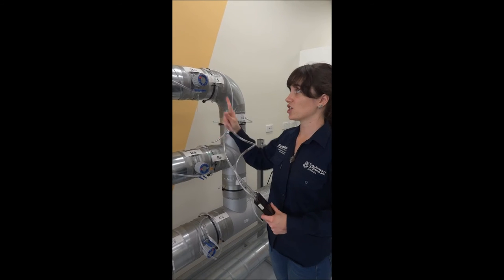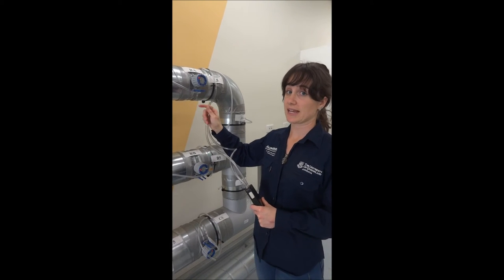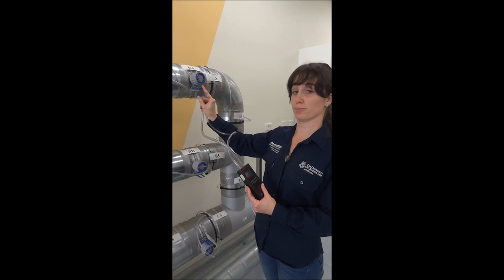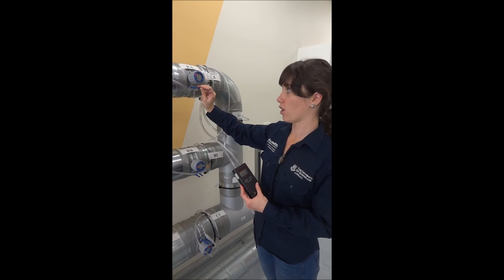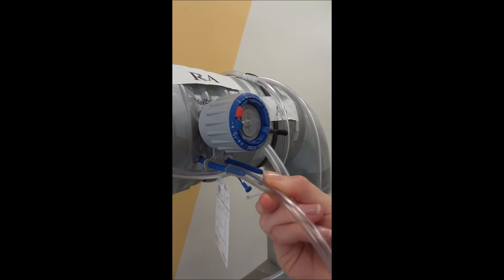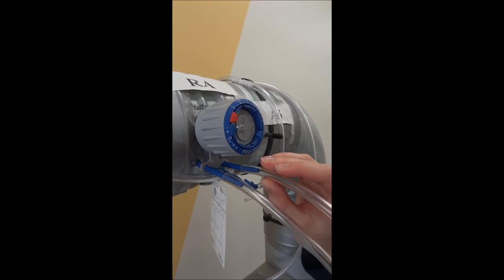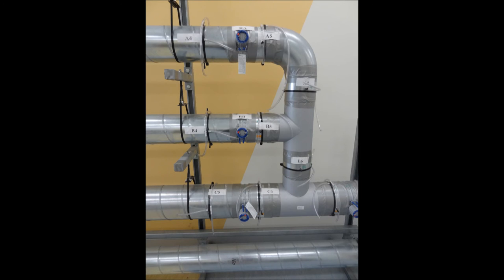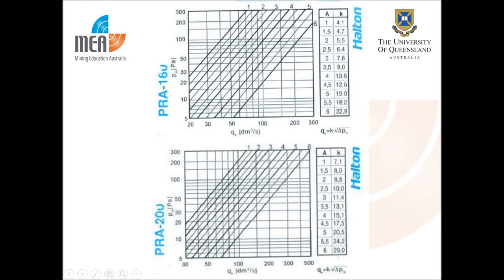The pressure change across these orifice plates is measured by connecting the digital manometer to the two blue outlets on the orifice plate attachment. This must be carried out in these three locations. The tables displayed are then used to calculate the k factors for each orifice plate using the A value of 6.